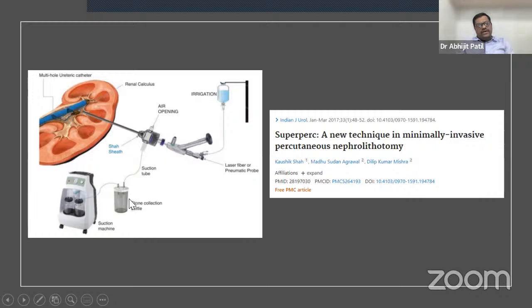And they have their own proprietary low power suction, not the conventional suction that we generally use, because if conventional suction is attached, it collapses the pelvicalyceal system. So people complain that the pelvicalyceal system gets collapsed, and this bleeding is because the suction attached to the sheath is a conventional suction. If we use this proprietary suction, it very well maintains the intrapelvic pressure, and you will not have collapsing of the system or any problem during stone disintegration.